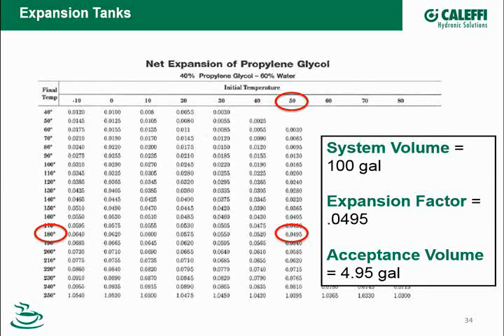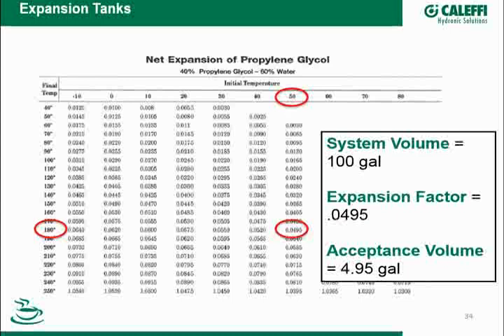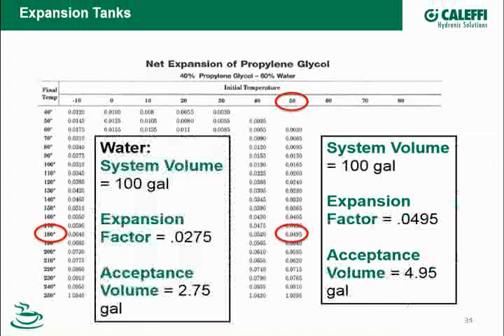0.0495. Let's go to my 100-gallon system. So it kind of gets it to a number that I find is a lot easier to get my hands around. A 100-gallon system, changing temperature from 50 to 180, gives 4.95 gallons of expanded water glycol mix. How does that compare with straight water? From a previous calculation, I know that my acceptance volume, straight water, is 2.75. Glycol expands significantly more than water.